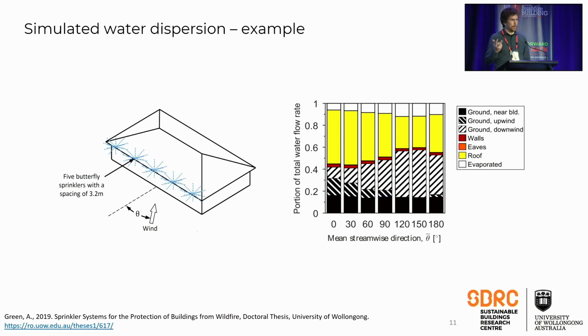This is the kind of result those simulations produce. This is for one of those systems, showing the breakdown of the ultimate endpoint of all the droplets we're tracking in the simulation. For example, in yellow, with different wind directions, how much of that water ends up on the roof of the building, and in dark red, the walls. For this sprinkler system, it's showing that about half, depending on wind direction, of the water ends up on the ground, which you'd expect since it's a symmetrical spray near the gutters. But there's quite a lot that gets evaporated in some cases, up to about 10% of the water.